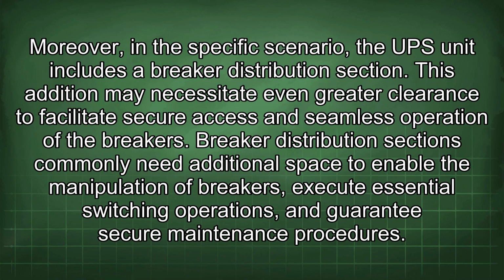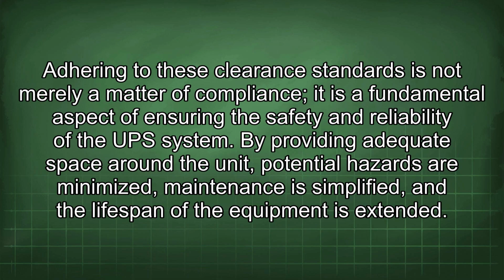Moreover, in this specific scenario, the UPS unit includes a breaker distribution section. This addition may necessitate even greater clearance to facilitate secure access and seamless operation of the breakers. Breaker distribution sections commonly need additional space to enable the manipulation of breakers, execute essential switching operations, and guarantee secure maintenance procedures. Adhering to these clearance standards is not merely a matter of compliance, it is a fundamental aspect of ensuring the safety and reliability of the UPS system.